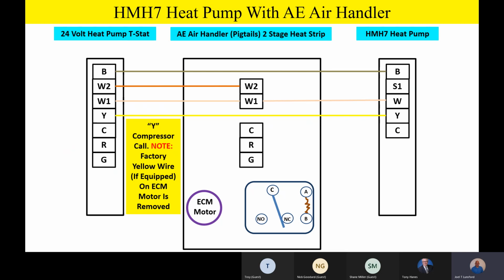And then the outdoor unit makes intelligent decisions by looking at suction line pressure, suction line transducers as far as pressure and temperature, suction line sensors, liquid line sensors. So it's taking a look at the refrigeration circuit and monitoring it. It's also monitoring outdoor ambient temperature. And it makes intelligent decisions on when to modulate with just a simple single Y signal going outside to call for compressor operation. I think that's just one of the coolest things around, is the fact that this unit is so simple to hook up, but it's got a lot of features and a lot of comfort capability.